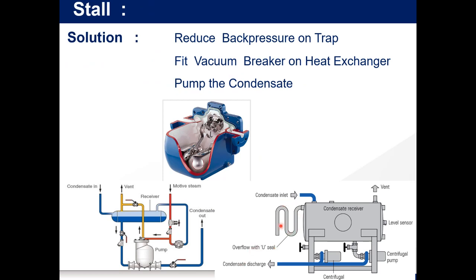So the overflow, the U-seal, I've been to many customer sites where this is quite short. So we would recommend that you make this U-seal as long as possible. The reason being is that in here, we keep water as a seal, as a plug. It's simply for overflow from the receiver. If this is too short, you will find the pressure of the steam here will blast this plug out, and what you'll see on site is steam venting from here. That's usually indicating that the water seal is gone, potentially because the U-seal isn't long enough.